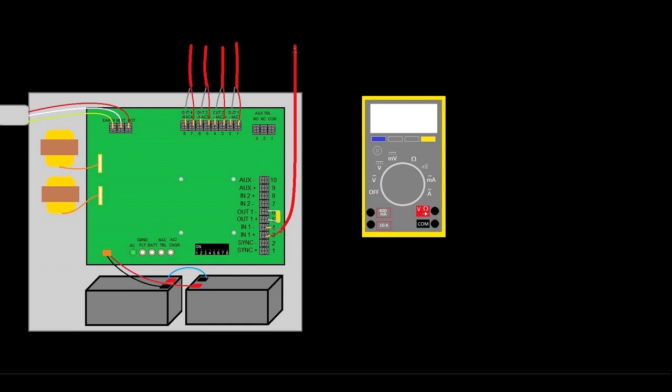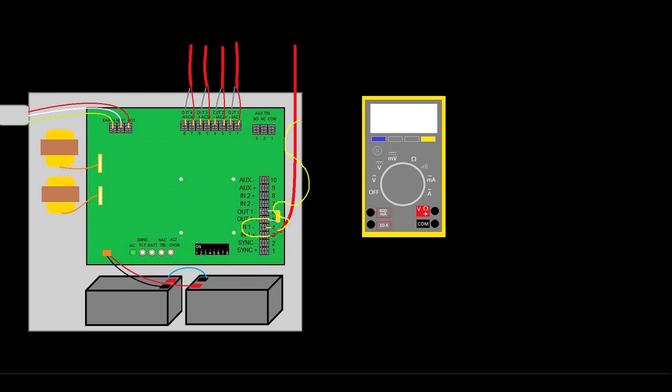That would show itself on whatever is triggering your FCPS. This is a point I did not make in the last video and I probably should have. If you look down here at the input side, whatever is triggering your power supply, whether that's a NAC off of your main fire panel or a control module that's going to open up. The positive side will open up on a trouble, causing this circuit here to not see its end of line resistor. So when there's a trouble that opens, you get a trouble on whatever that is. So the FCPS itself does not supervise the input. It's whatever's triggering it that is supervising it.